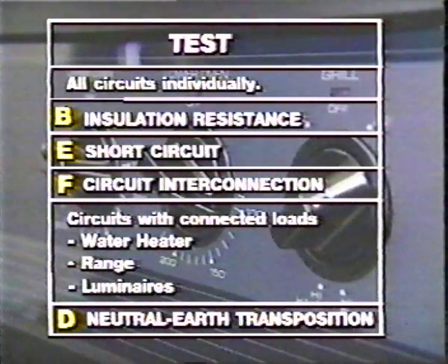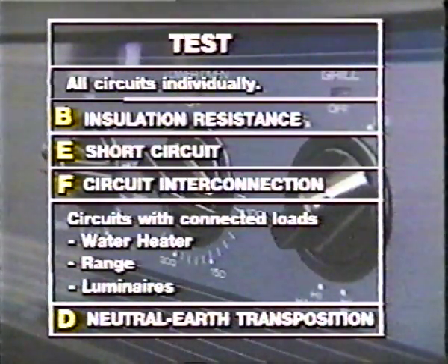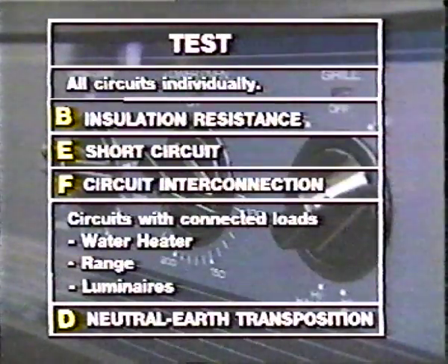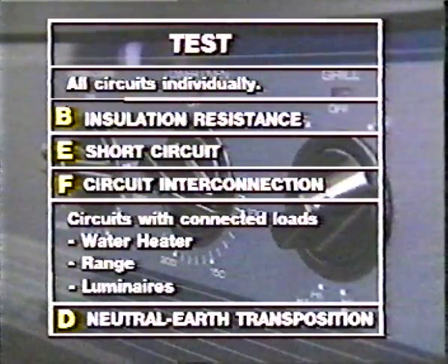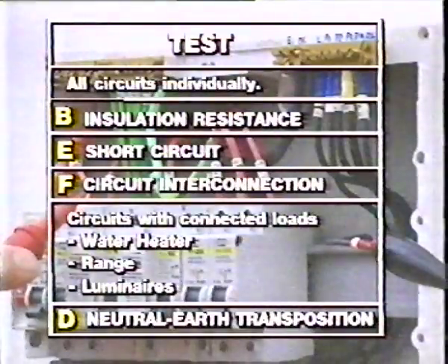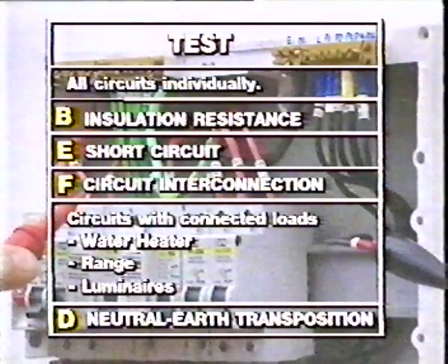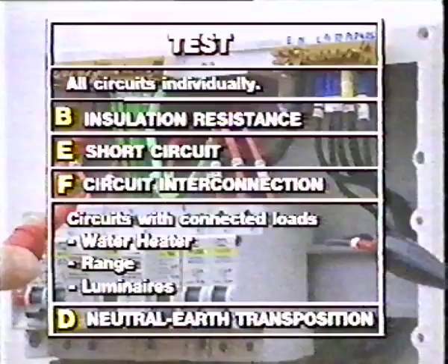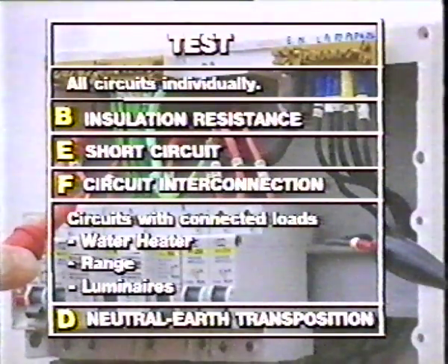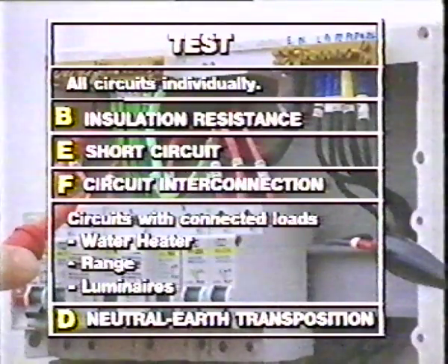Neutral earth transpositions for circuits with connected loads such as water heaters, luminaires and ranges should now be tested as in test D. In this test, correct connection has been made when load resistance is measured between active and neutral, and an open circuit is indicated when testing between active and earth and neutral and earth.